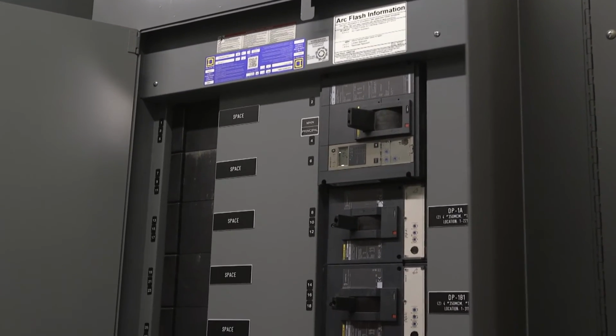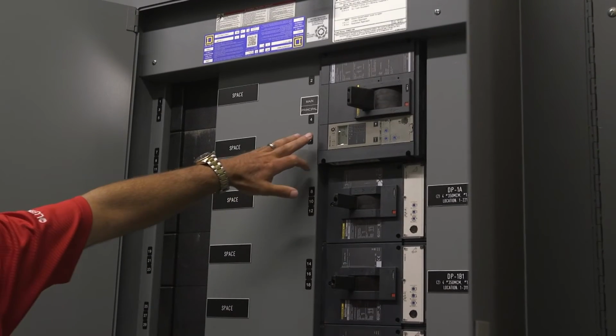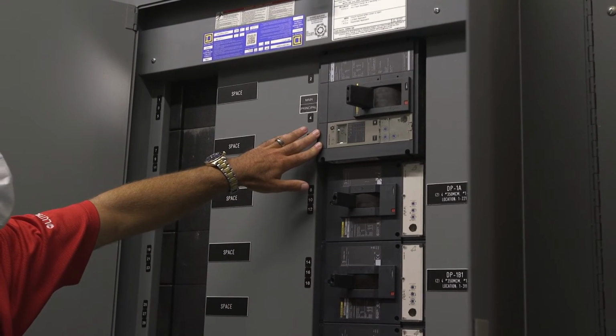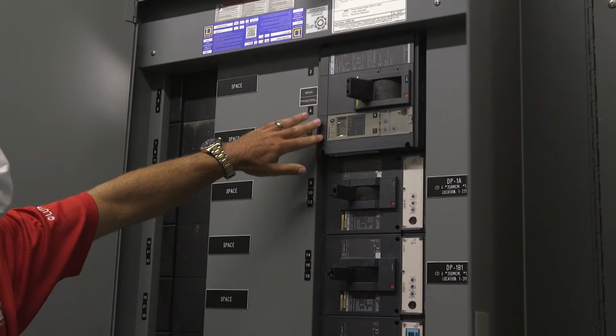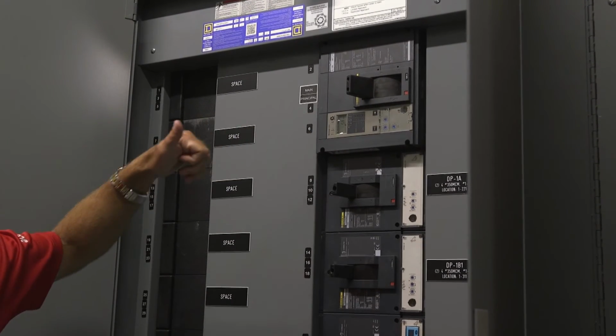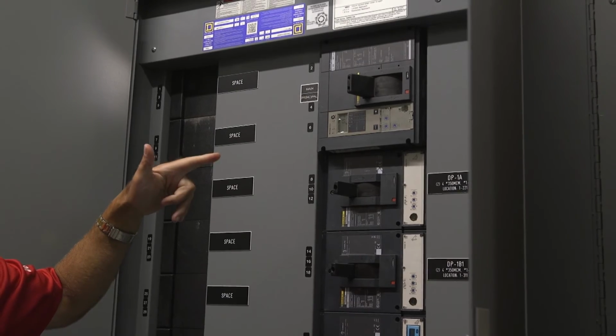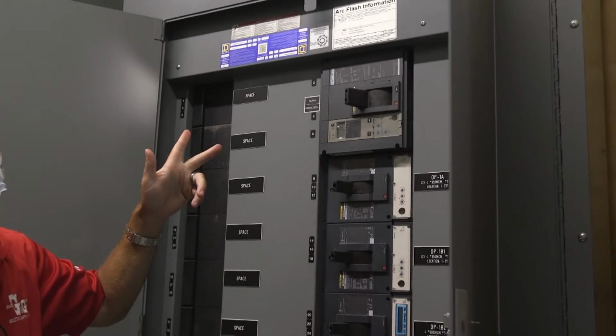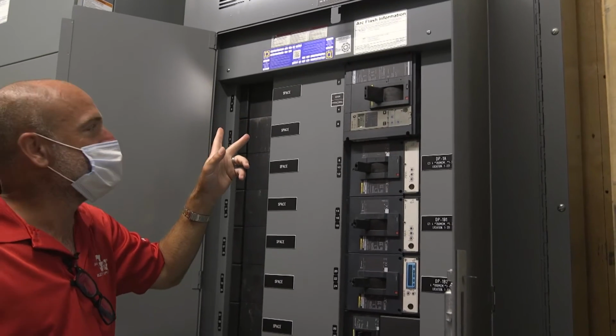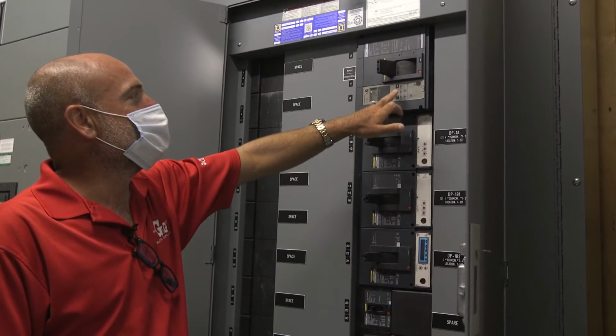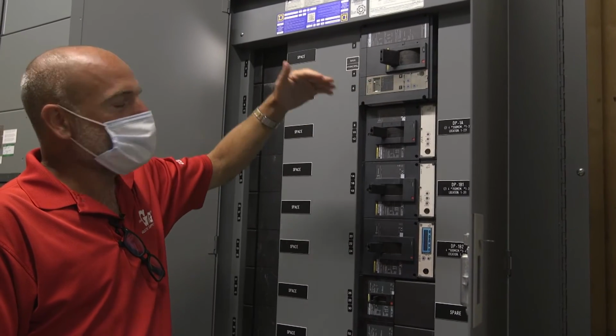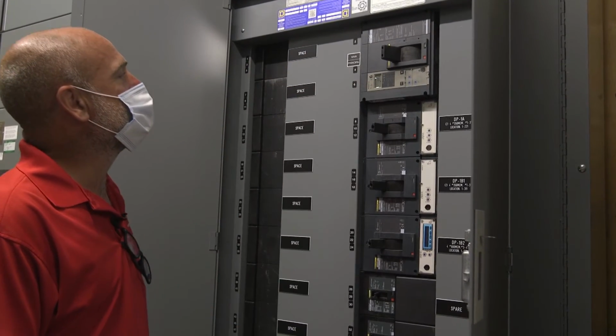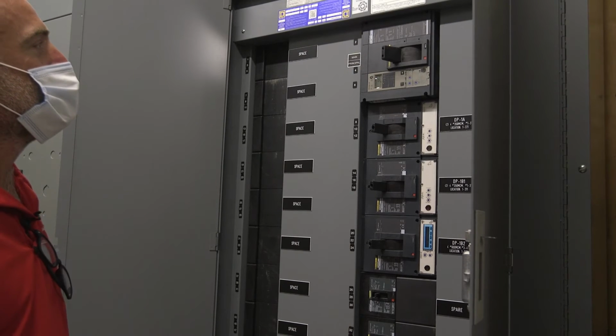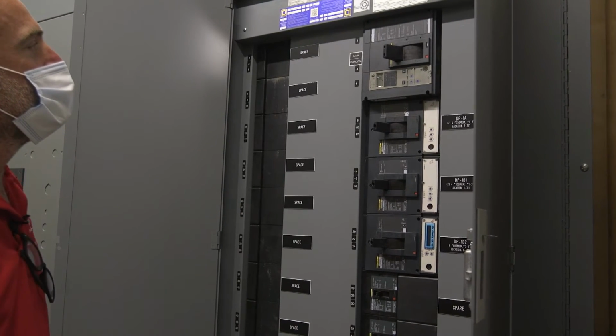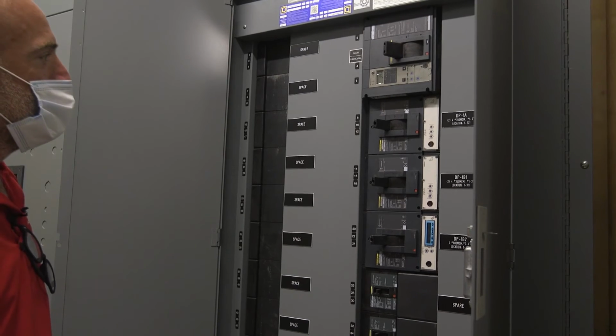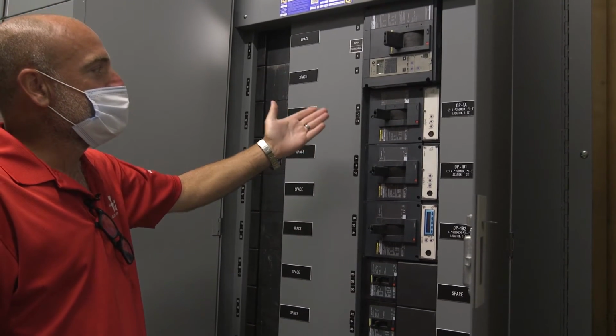Moving to the circuit breakers. This circuit breaker, I don't know if you can see, has an adjustable trip, and there's also a meter reading on here, which shows your amps per phase, your volts per phase, your peak high amperage. It's just a menu button and a scroll button that'll take you through all of the different visual cues that are there. Once again, these are the same breakers.